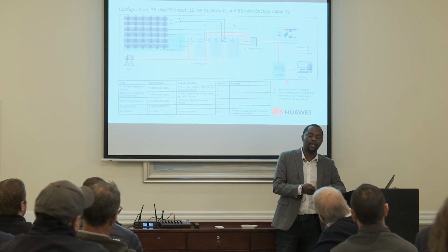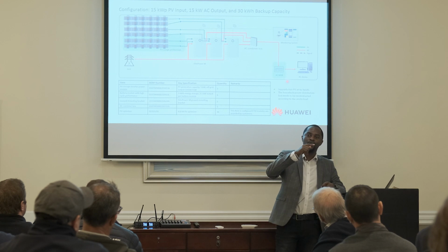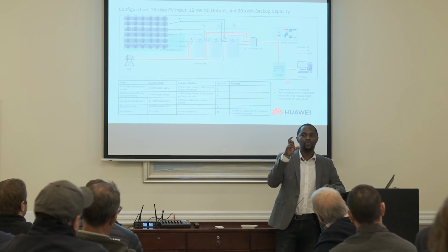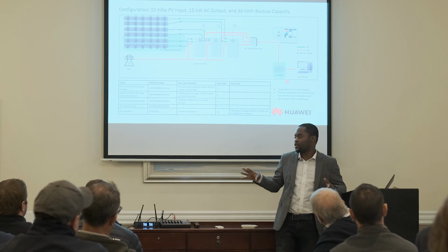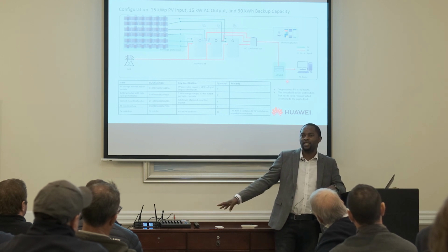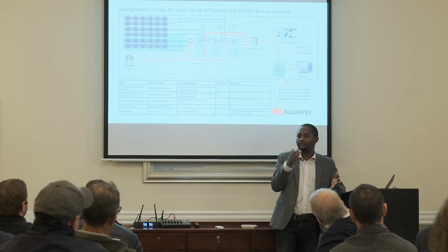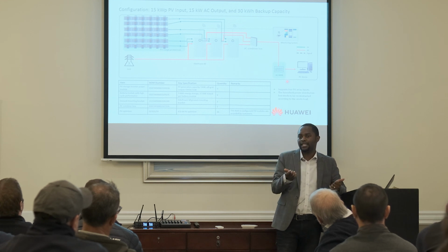But now with the Huawei one, it's UPS based. Even if your voltage is jumping up and down, but it's within that 90 to 300, then that generator can be used with this inverter. Then the frequency range is also wider, from 46.5 to 53 Hz.